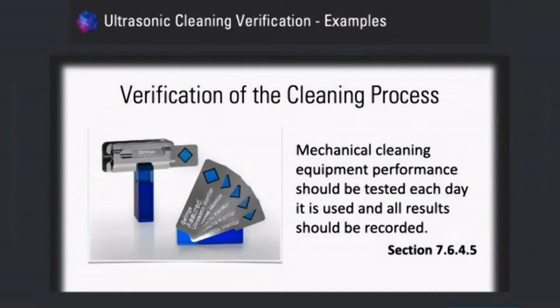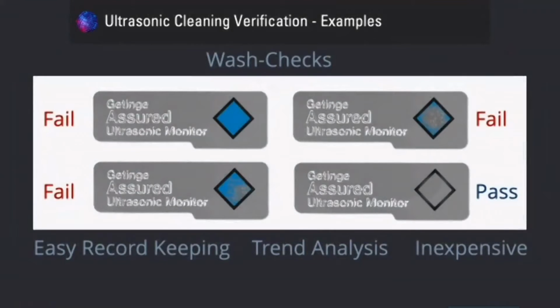Now, a very easy to use verification for cleaning is a thing called wash checks. For verification, mechanical cleaning equipment performance should be tested each day it is used, and all results should be recorded. And in this case here, with the item you see, wash checks are very good for easy record keeping and for trend analysis, and they're very inexpensive. There are several verification products out there. I'm showing you this one because you have these metallized coupons with a blue soil on them.